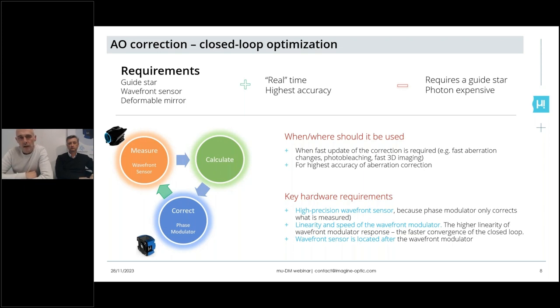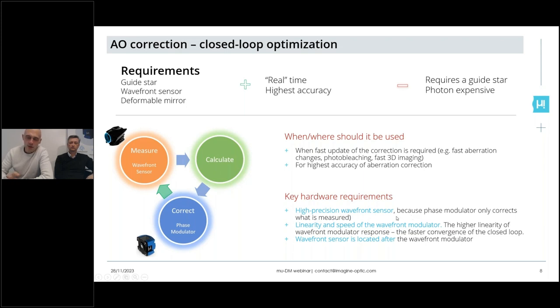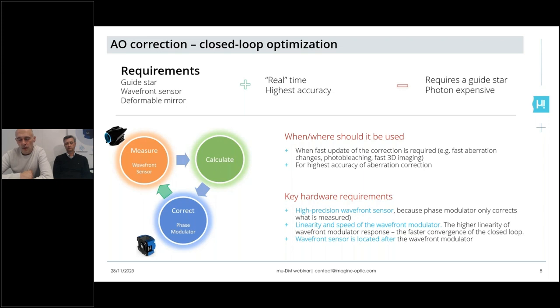The closed-loop approach is recognized as highly accurate — more accurate than the indirect wavefront sensing approach. For its implementation, a high-precision wavefront sensor is required, because the wavefront sensing accuracy is what drives the efficacy of the method. The phase modulator is only correcting what is measured by the wavefront sensor. High linearity and speed of the wavefront modulator are required in order to optimize the speed of convergence of the closed loop.